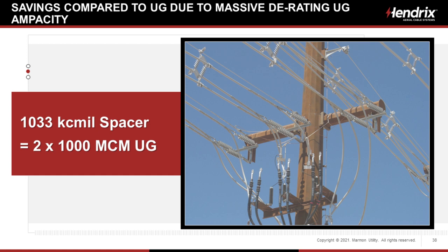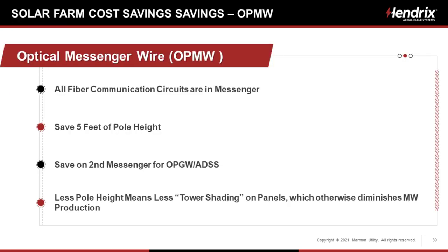If you look at this next slide, if you can see that, this was 10, 11, 12 years ago, when we were still building dead-end poles outside the substation fence before we convinced the designers to go right to the substation bus. You can see you're coming off. I've got a 1033 kcmil spacer cable circuit. And in order to bring that underground, I had to use two 1,000 MCM underground cables because of the derating. So that 1033 kcmil spacer cable had more ampacity than paralleled 1,000 MCM underground cables. That's a lot of money. That's a massive savings.